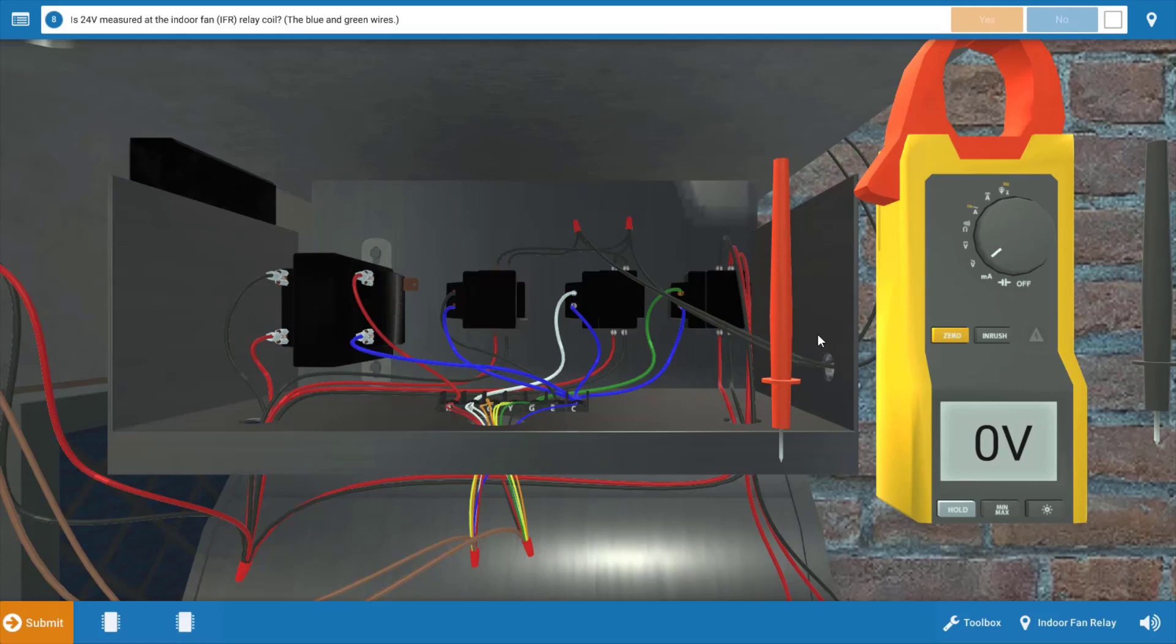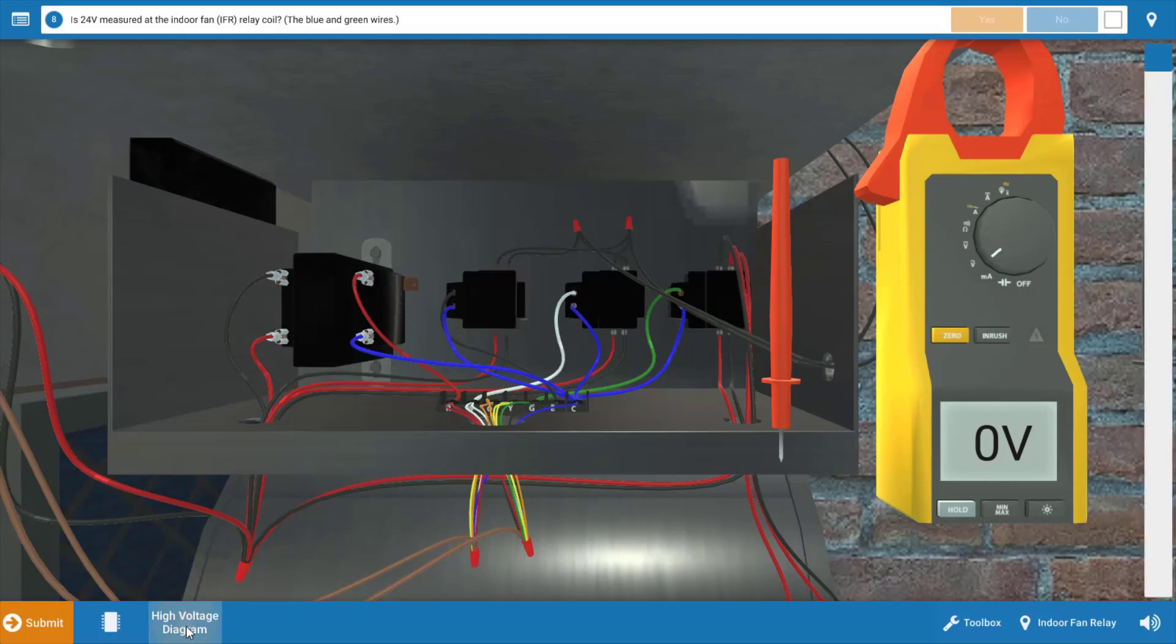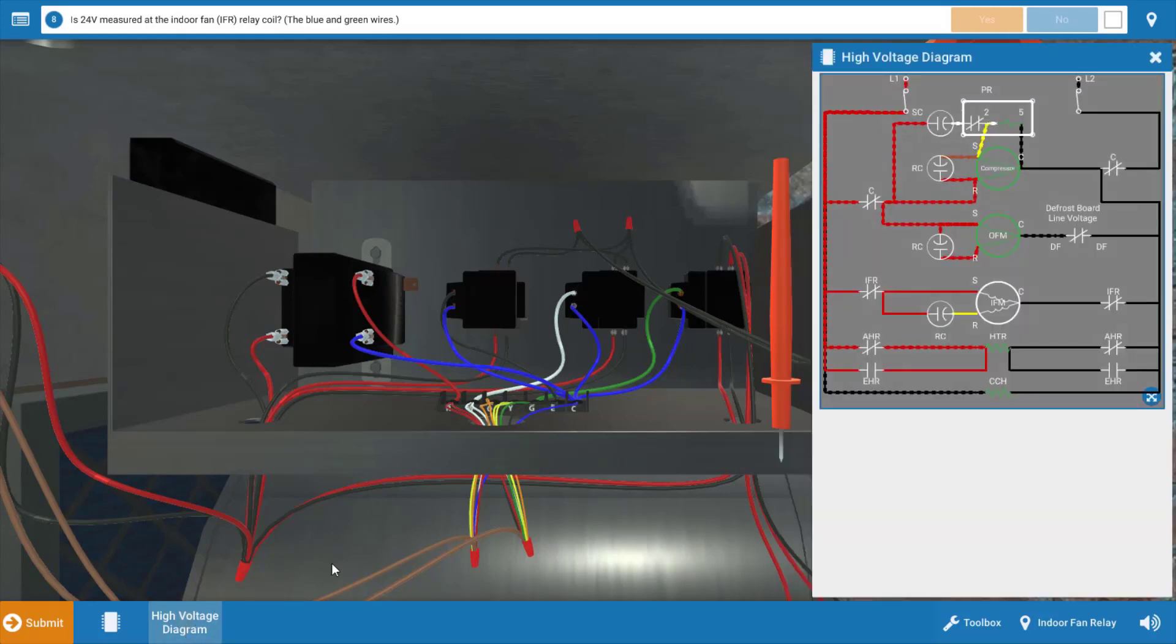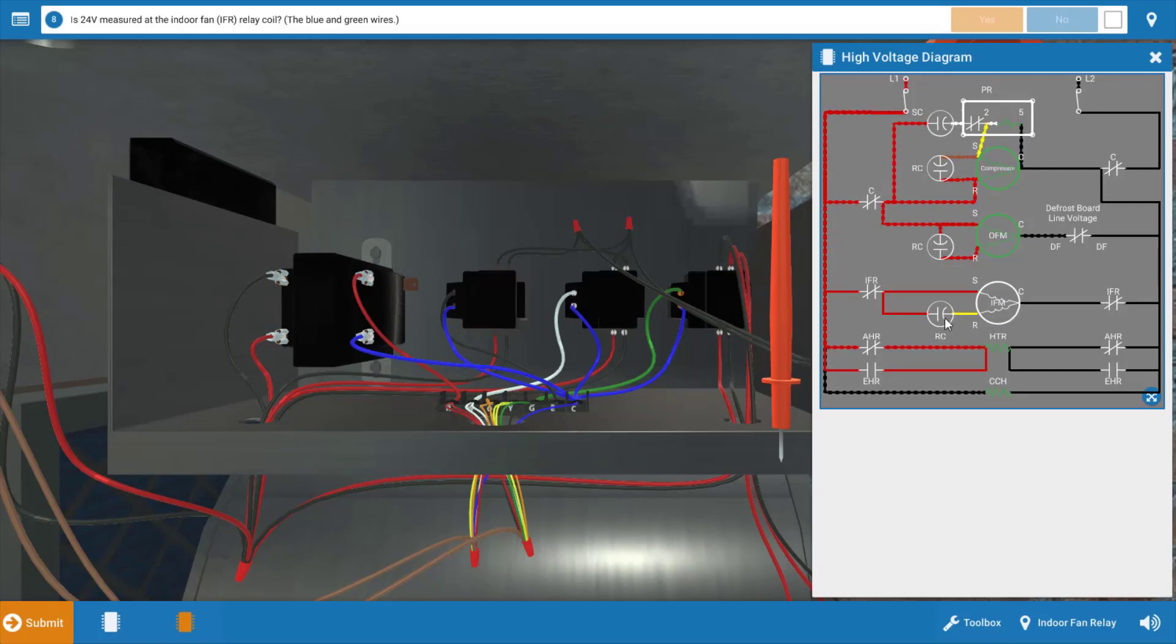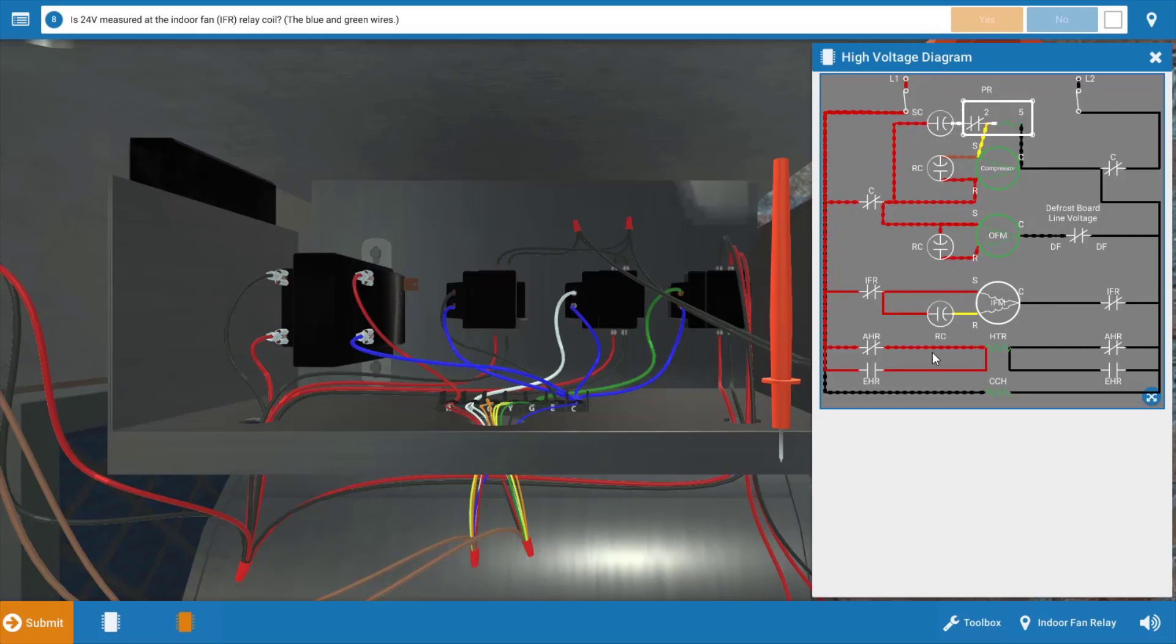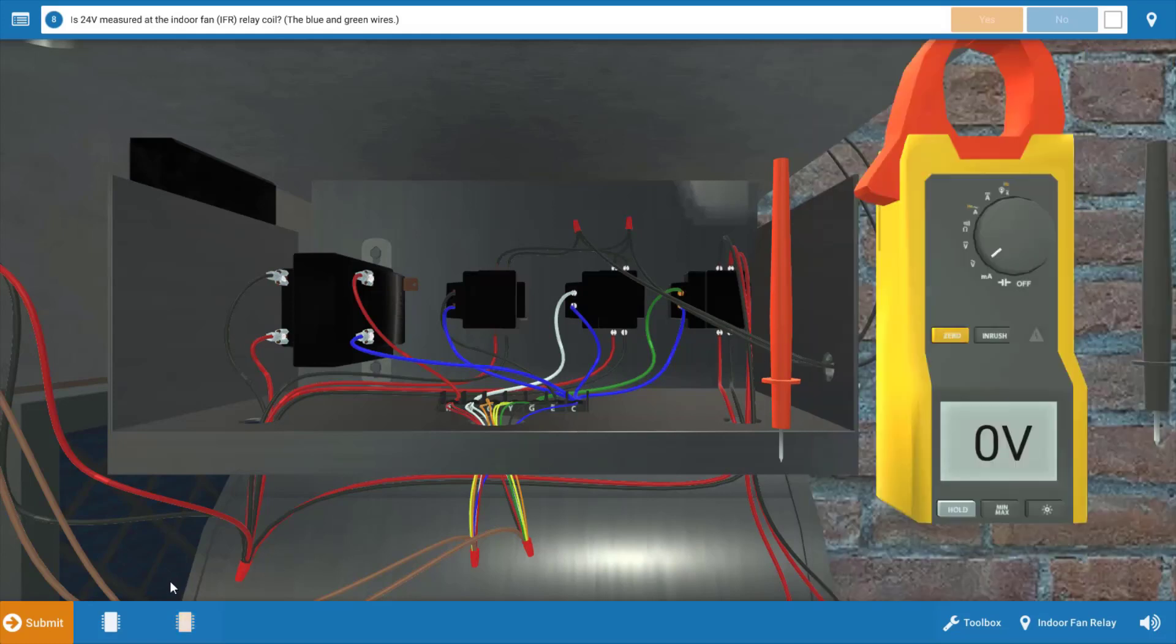Before I take any voltage readings here, I'm going to take out the wiring diagrams and come up with an inventory of possible causes, starting with the line voltage diagram. We can see the indoor fan motor is right here towards the bottom of the page. It's possible we have an open winding in the motor, a faulty run capacitor, or that these indoor fan relay contacts are not closing, which means the coil or the fan relay itself could be faulty.